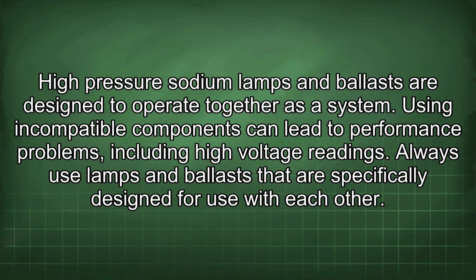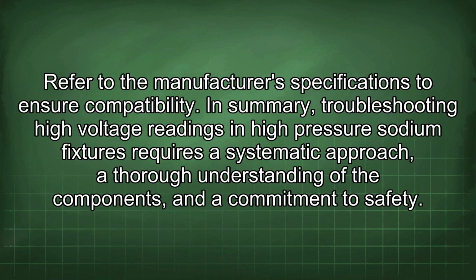Using incompatible components can lead to performance problems, including high voltage readings. Always use lamps and ballasts that are specifically designed for use with each other. Refer to the manufacturer's specifications to ensure compatibility.